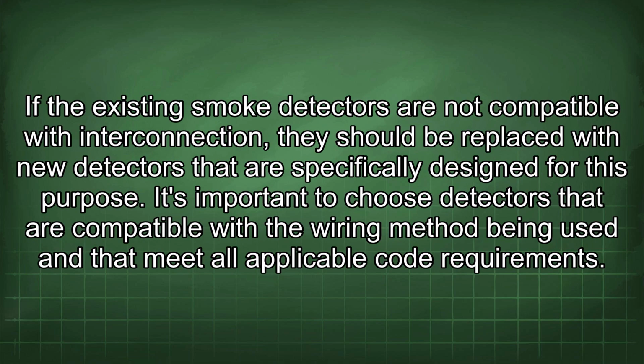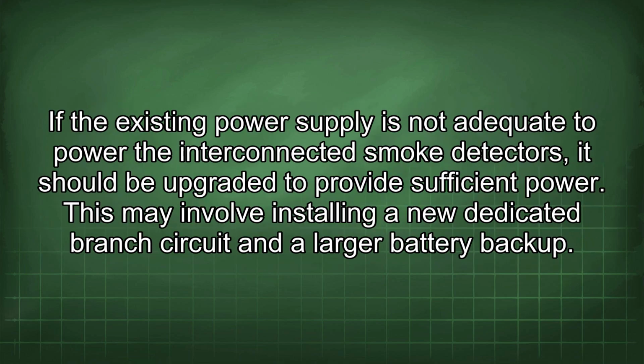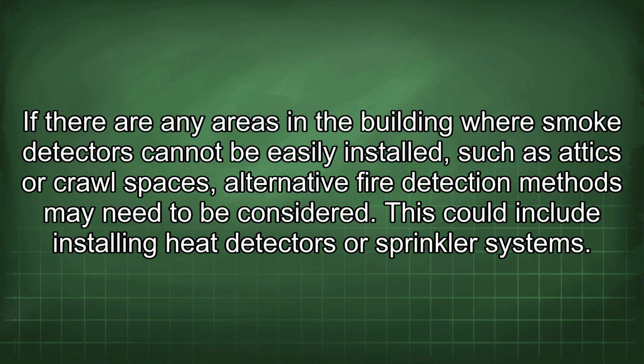If the existing smoke detectors are not compatible with interconnection, they should be replaced with new detectors that are specifically designed for this purpose. It's important to choose detectors that are compatible with the wiring method being used and that meet all applicable code requirements. If the existing power supply is not adequate to power the interconnected smoke detectors, it should be upgraded to provide sufficient power. This may involve installing a new dedicated branch circuit and a larger battery backup. If there are any areas in the building where smoke detectors cannot be easily installed, such as attics or crawl spaces, alternative fire detection methods may need to be considered. This could include installing heat detectors or sprinkler systems.